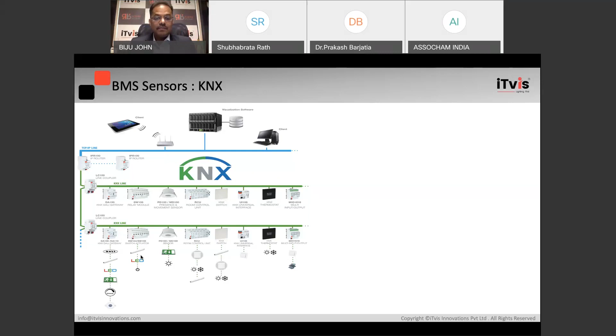So this KNX Basic and KNX Mini sensor technology, what you could see over here, is a sensor which is used in this type of application. If you use a KNX protocol sensor in the system, this sensor will always tell if somebody is under me or not. It will always tell the system what the lux level under me is. So the algorithm you are setting in the software can be based on the message coming from the KNX sensor.